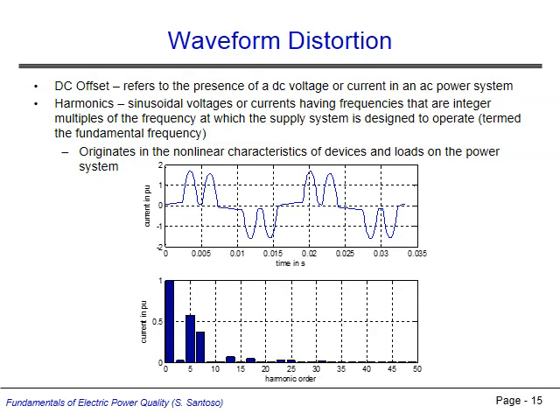A DC offset is the presence of a DC voltage or current in an AC power system. When such an offset is present, the average voltage or current of the system will be non-zero. Harmonics are sinusoidal components of voltage or current waveforms that have frequencies that are integer multiples of the fundamental power frequency. Harmonics occur due to loads on the power system that have non-linear voltage current characteristics. The figure here shows a current waveform with significant harmonic components. The lower graph shows the waveform's spectral content, identifying large contributions from the fifth and seventh harmonics.